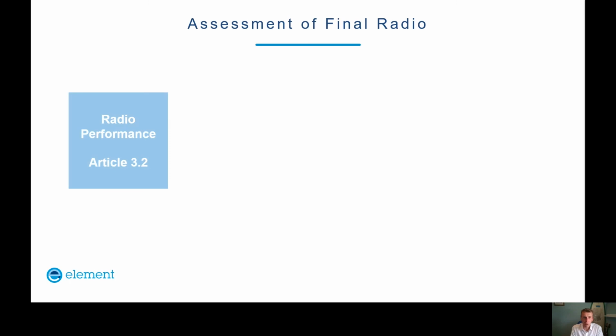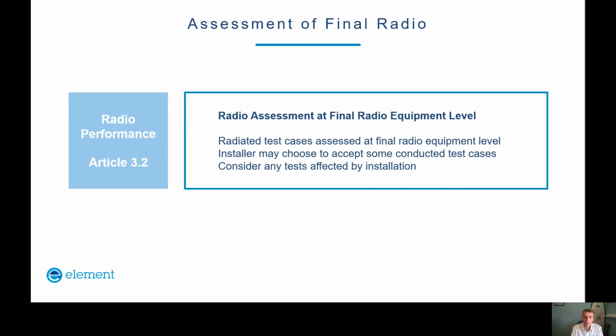For radio performance, unlike safety and EMC where you start testing from fresh, you can start to use more test results from the radio module manufacturer. The assessment is at the final radio equipment level, but the manufacturer may choose that some tests are not needed, on a case-by-case basis.